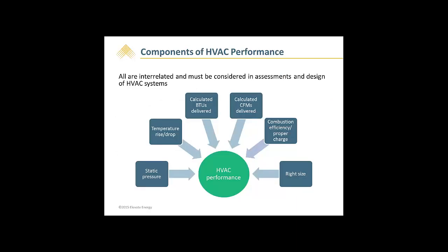This graphic depicts the components of HVAC performance. If any of these measures or calculations are outside of manufacturer's specifications, optimal efficiency will be affected. HVAC performance testing has 5 components. Static pressure is the resistance to the airflow in the system. Temperature rise is the rise in temperature in the heating mode. Manufacturers typically provide a range, which is usually around 40 to 70 degrees. The drop refers to the decrease in temperature when the air conditioner is running, and that's typically around 20 degrees.